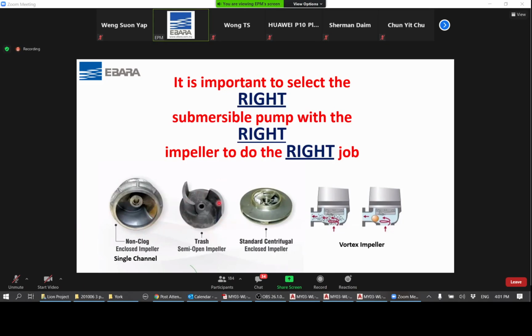Okay, and on the other case, this is what we call a semi-open pump impeller, so it can handle a little bit more than dirty water, but also some form of impurity like leaves and maybe light fibers and plastics and so on. And even in some cases, we have what we call a vortex impeller. You can see from the design here, the impeller actually creates a vortex or a vacuum principle where the water does not flow through the impeller, but rather is sucked out with the impurity.